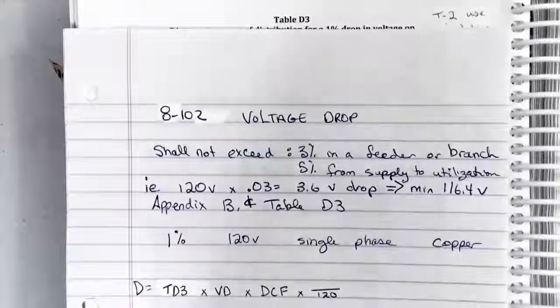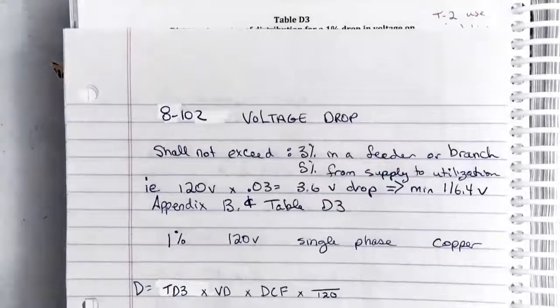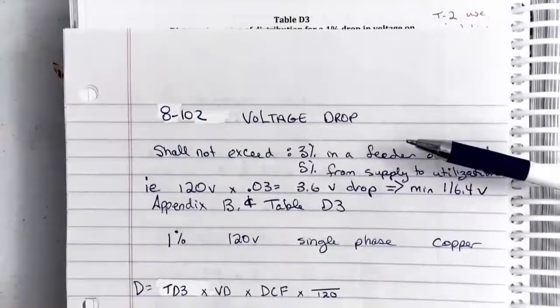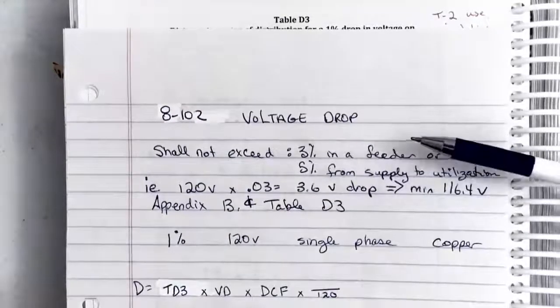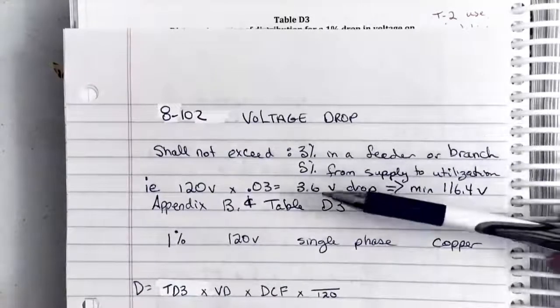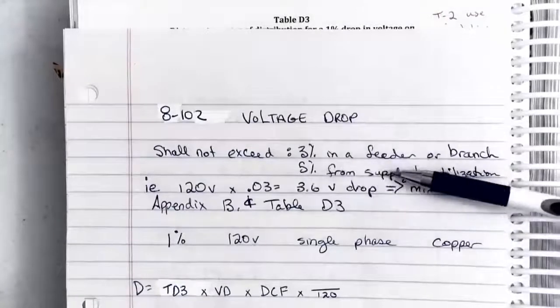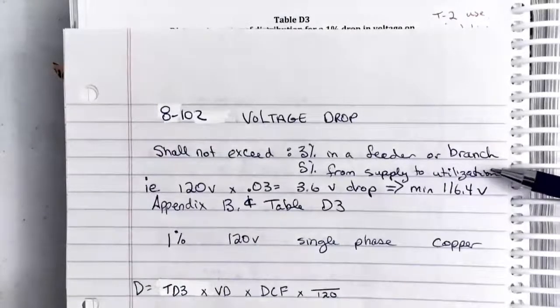Hey everybody, let's look at Rule 8102 in the Electrical Codebook for Canada. It's talking about the voltage drop in each circuit. 8102 tells us that we cannot exceed 3% voltage drop in a feeder or branch circuit, or overall we can't exceed 5% all the way from where the supply comes into the building out to the point of utilization, say out to a receptacle or load.